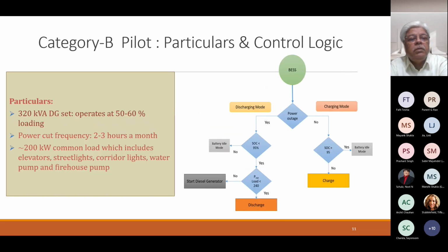What is shown there is the control logic for a 320 kVA DG set, which operated at about 50 to 60% loading when the project was initiated. At that point, the power cut was about 2 to 3 hours a month. The common critical load, which covered the elevator, street light, corridors, water pump, and fire pump, was of the order of 200 kilowatt.